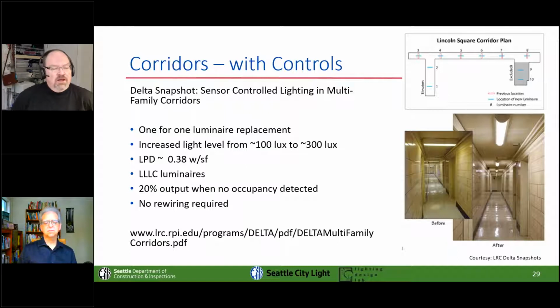One interesting thing, they went ahead and increased the light level from 100 lux, 10 foot-candles, to 300 lux. It's not necessarily something that you would have to do, but it is an interesting thing from a lighting power density standpoint, because they're at 0.38 watts per square foot, which is actually even increasing up to 30 foot-candles, which is higher than the recommended light level per the IES. They're at 0.38 watts per square foot, where our new code is 0.37 watts per square foot with no additional allowances, right? So by going ahead and doing this, they dropped to 20% light output when no occupancy is detected. And they didn't have to do any rewiring or anything to get that kind of controls bonus.